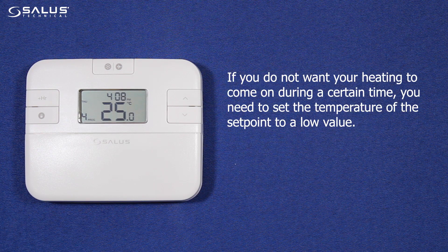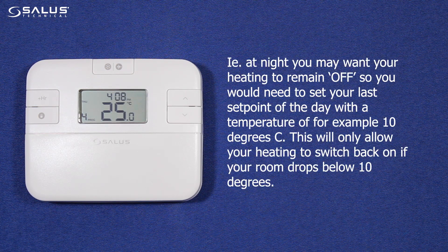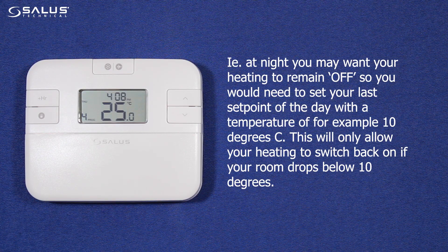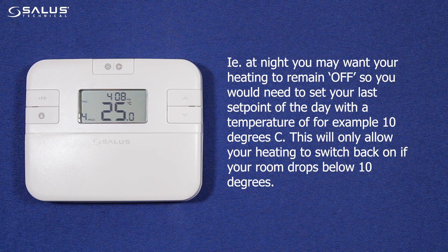If you do not want your heating to come on during a certain time, you need to set the temperature of the set point to a low value. For example, at night you may want your heating to remain off, so you would need to set your last set point of the day with a temperature of, for example, 10 degrees. This will only allow your heating to switch back on if your room drops below 10 degrees.